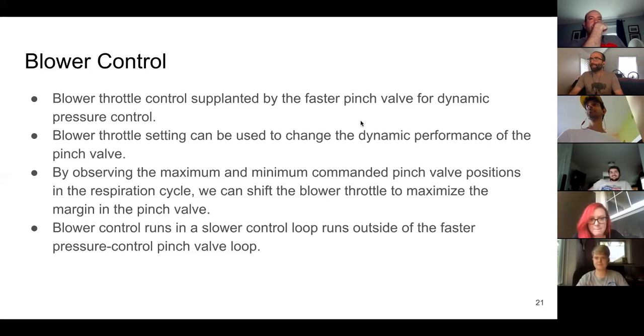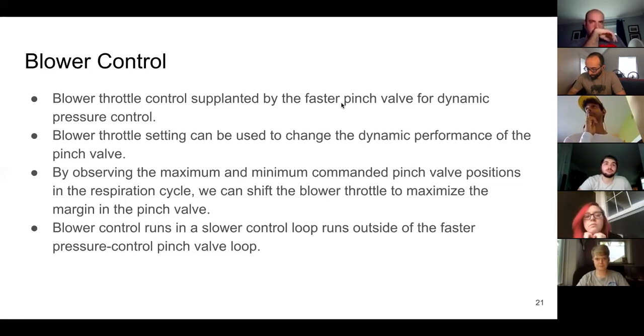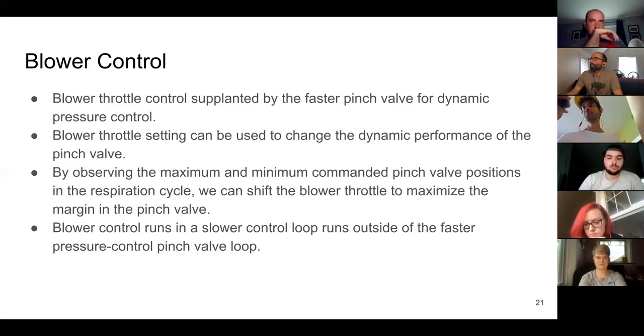I'll give a quick background. I think perhaps a better term for the IAV would be a stepper-driven pintle valve. Essentially, it's a cone-shaped plunger: imagine a cylindrical orifice, a pipe through which flow is going, and then a cone-shaped plunger goes into that pipe. As the diameter changes entering the pipe, it creates a variable-sized orifice, so it's essentially a variable resistance on the flow through that pipe. So perhaps we can call it the stepper-driven pintle.